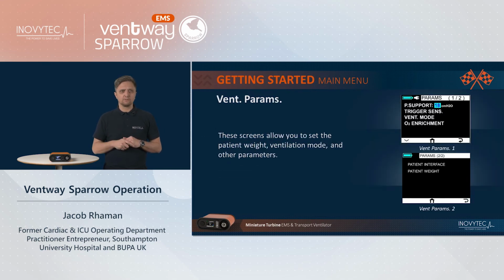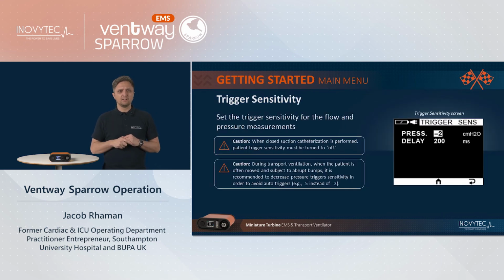Vent params or parameters. These screens allow you to set patient weight, ventilation mode and other parameters. Trigger sensitivity. Set the trigger sensitivity for the flow and the pressure measurements. Caution! When closed suction catheterization is performed, patient trigger sensitivity must be turned off. Another caution. During transport ventilation, when the patient is often moved and subject to abrupt bumps, it is recommended to decrease pressure triggers in order to avoid auto triggers. For example, you can go to -5 instead of -2.